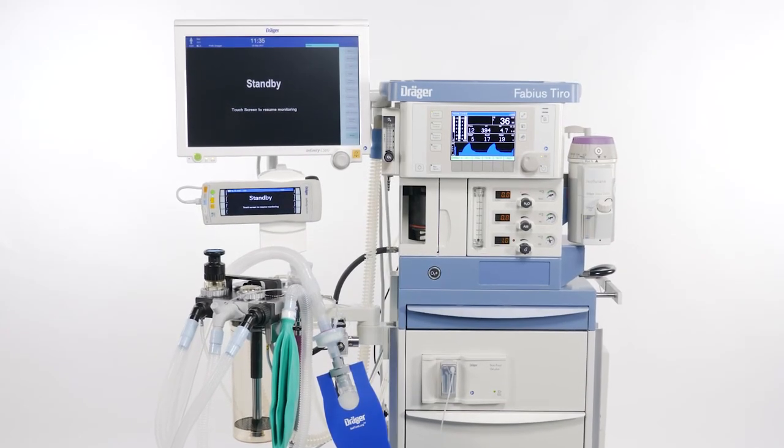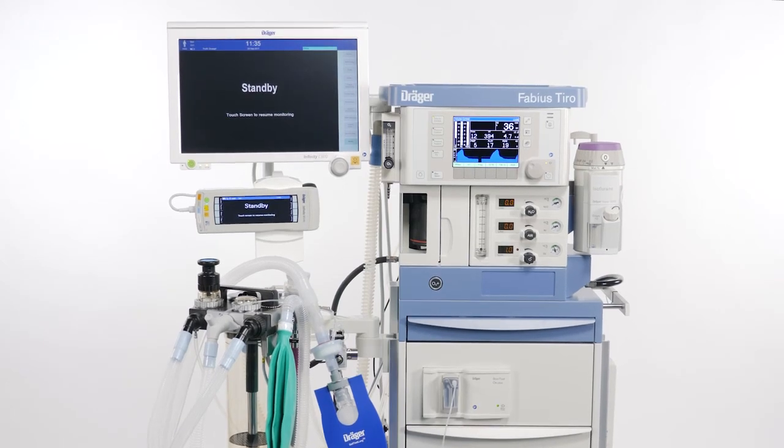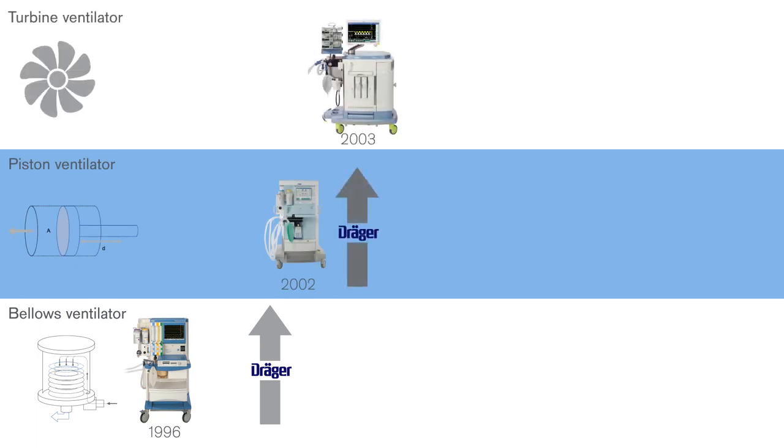The Draeger Fabius Tiro anaesthesia device is equipped with an electronically controlled and electrically driven piston ventilator.